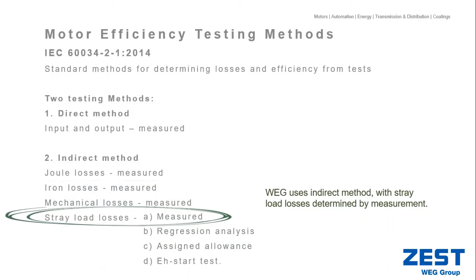So the standard also calls, as I said earlier, that on the rating plate of the electric motor, we need to clearly state what the efficiency class is, and together with that, we also need to indicate what the efficiencies would be at 100, 75, and 50% load. That is also just to show you, because we often know that electric motors don't always run at 100% load. Sometimes they are oversized, and also to ensure that the efficiency of that motor has a flat curve, which means if the motor is running at half, three-quarter, or full load, you're still getting the benefit of the efficiency level that the motor is stated at.